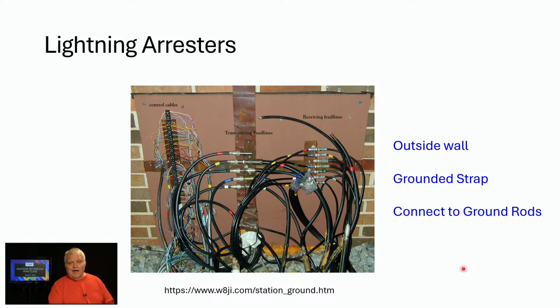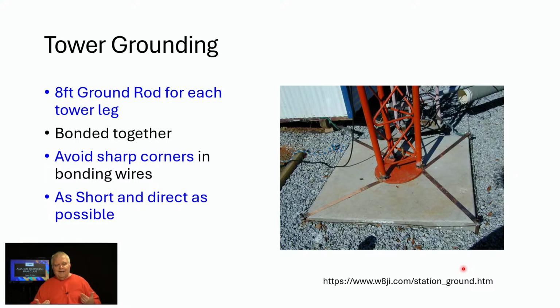Oh, you're adventurous, you're going to put up a tower? Well, if you put up an antenna tower, whether 30 feet tall or 100 feet tall, you want a ground rod for each tower leg. Here we have a three-legged tower, and we've got four — we did a little extra. You've got a flat copper strap running out, CAD welded here, to an 8-foot ground rod driven into the ground. There's very likely a copper ring of flat copper strap or cable that rings the bottom of the tower to bond all these ground rods together. Again, avoid sharp corners, and keep it as short and direct as possible.